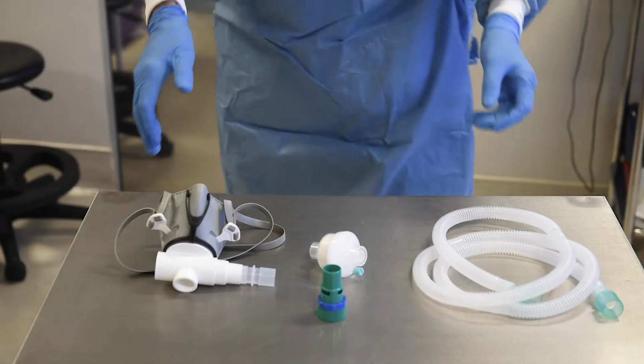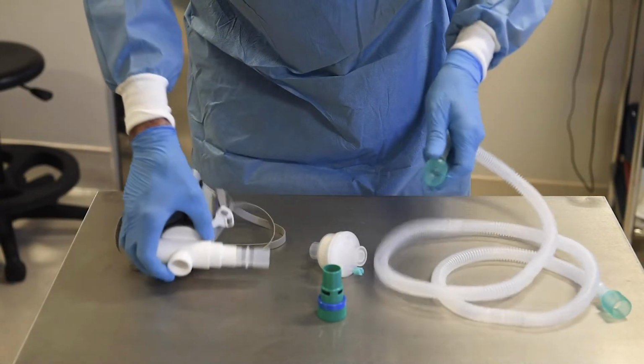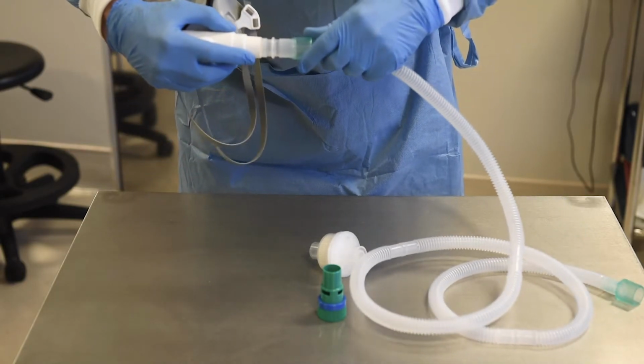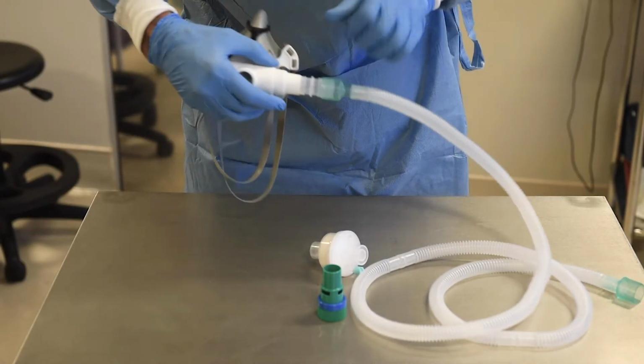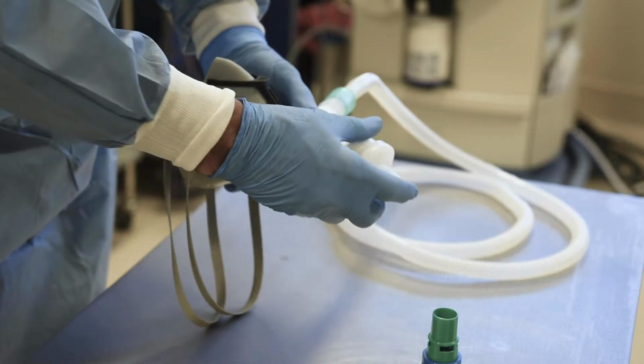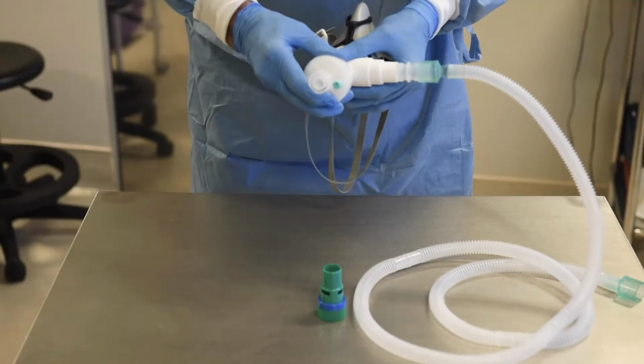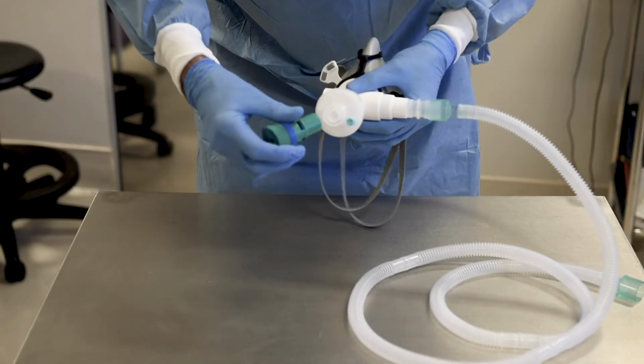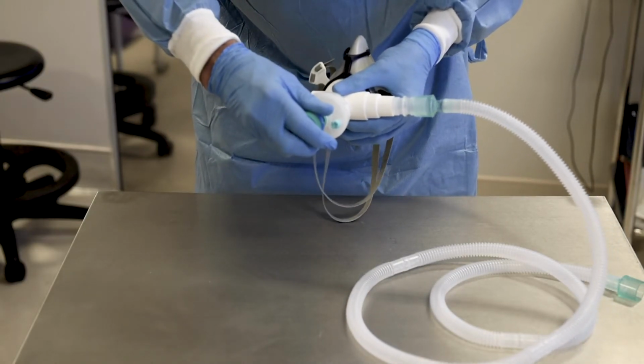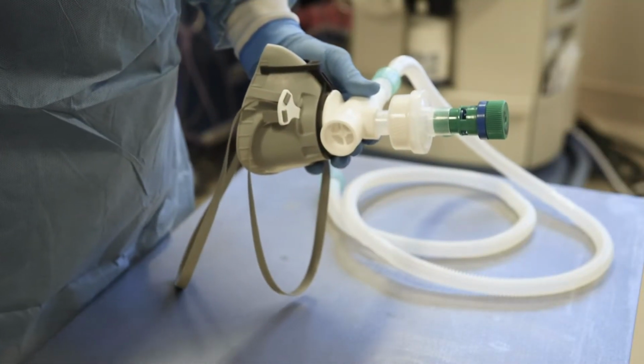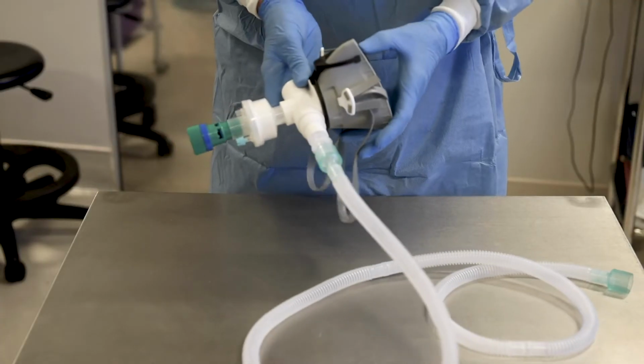Now go to your mask and connect the 22mm corrugated anesthetic tubing to the mask. On the expiratory side of the mask, you need to put a viral filter. Please make sure that this is a new viral filter, as these filters do not last forever. Once you've put the filter in place, please put a PEEP valve onto the other side of the viral filter.